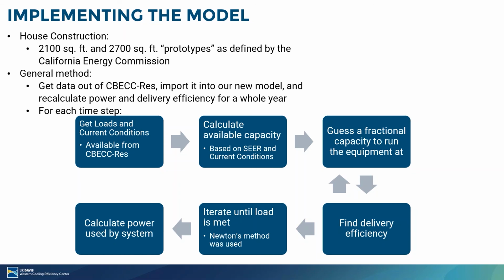Our general method is to get the loads and current conditions from the current modeling software. It gives us the load on the building, the weather, the attic temperature, stuff like that. From there, we can get the available capacity. If it's really hot out and humid, the weather does affect the efficiency and available capacity of the condenser unit and the indoor fan. So we can calculate that.